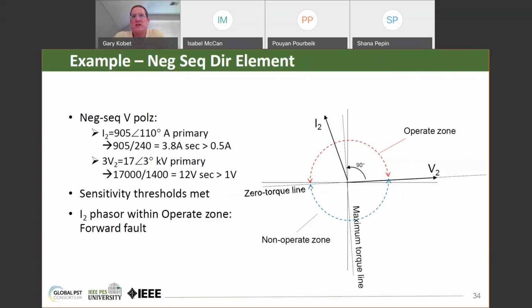Now, this decision is contingent on there being enough negative sequence quantity, voltage and current, for the relay to make a phase angle determination. If I have 3 or 4 amps secondary of negative sequence current and 12 volts secondary of negative sequence voltage, then the relay is going to be able to make that decision. But relays have directional element thresholds where you have to have, say, 1 volt of negative sequence voltage and a half amp or 1 amp of negative sequence current.